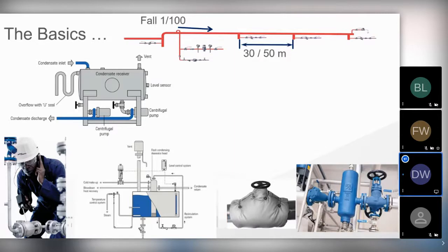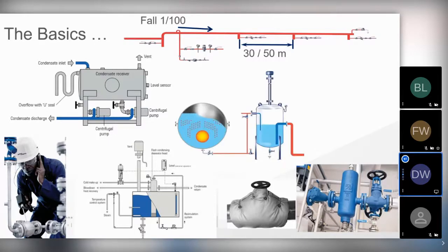We want to reduce heat losses by keeping the insulation at the best possible level that we can. We want to keep the blowdown losses to an absolute minimum. We want to move away from manual blowdown controls, and we want to move towards a timed actuator on the bottom blowdown valve and conductivity probes ahead of a modulating valve to address the TDS blowdown. By keeping the TDS and the bottom blowdown at the prescribed level, we can reduce those heat losses significantly.